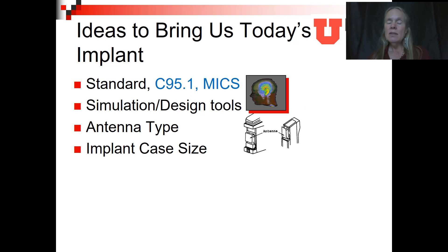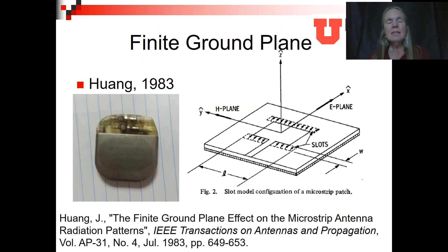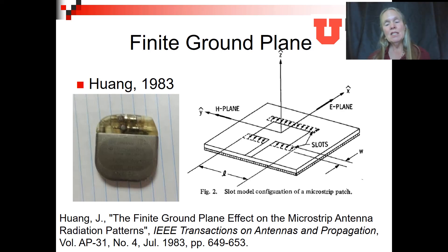With a standard, some simulation and design tools, and a good antenna type, the next thing to consider is the implant case size. This is a picture of a pacemaker — one that was inside one of my students. In 1983, there was a lot of work done on finite ground planes. A pacemaker is definitely a small and finite ground plane. Being able to understand how antennas behave when their ground plane is no longer infinite was very important to the design of antennas for medical devices.